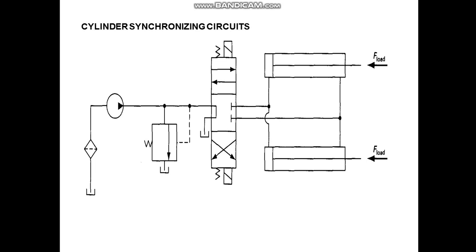Let us try to understand the cylinder synchronization circuit. We need to understand the difference between sequencing and synchronization. Sequencing means we have to achieve the motion of multiple cylinders one after the other — extension of cylinder 1 takes place first, then at the end of extension of cylinder 1, extension of cylinder 2 will start, then cylinder 3 and so on. In retraction, retraction of cylinder 3 starts first, then cylinder 2, then cylinder 1. That was sequencing.